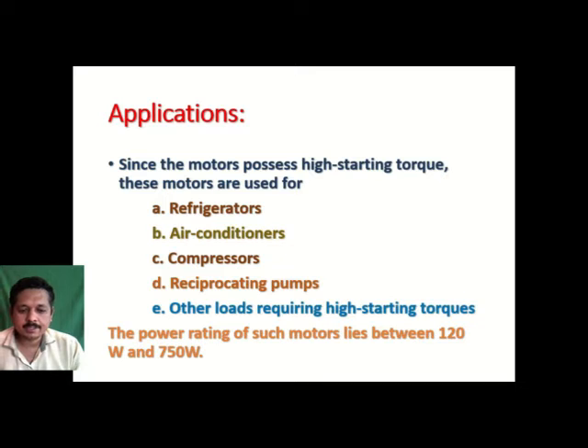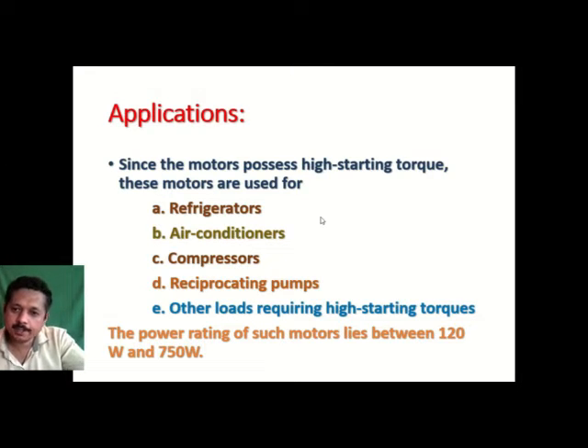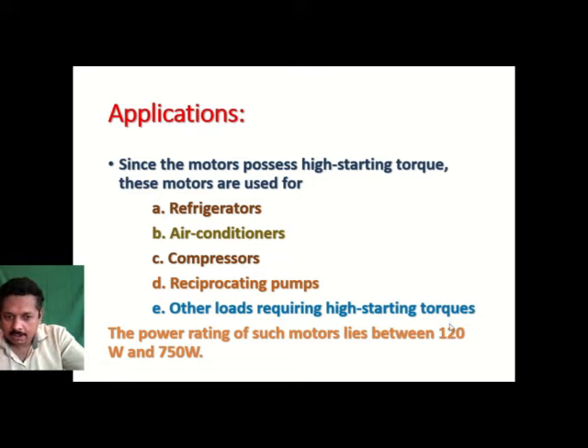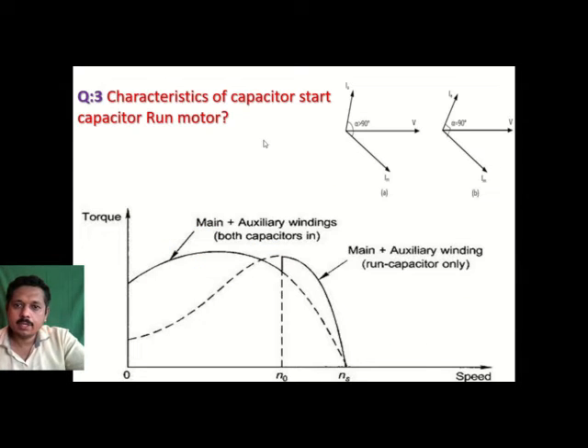Since this motor possesses very high starting torque, it can be used where the application requires high starting torque. Applications include refrigerators, air conditioners, compressors, reciprocating pumps, and other loads requiring high starting torque. The power requirement limit for these applications is between 120 watts to 750 watts.